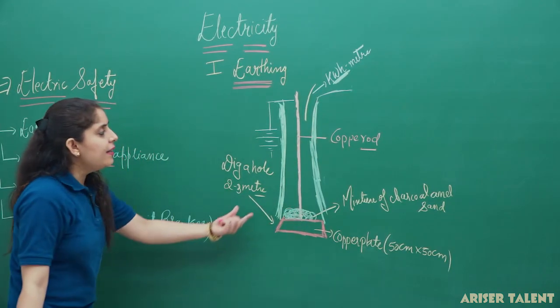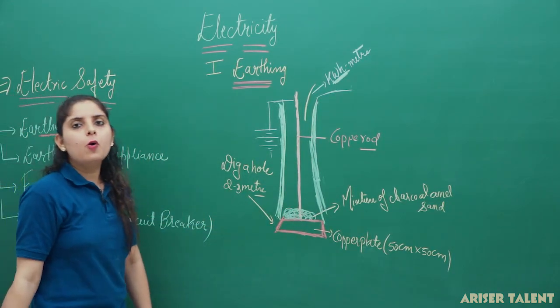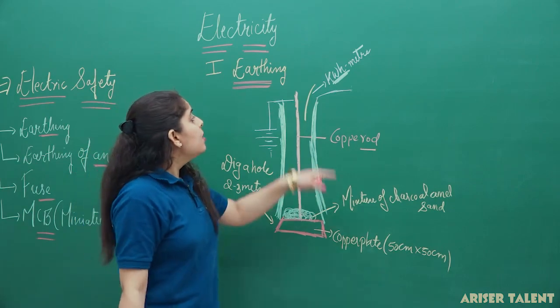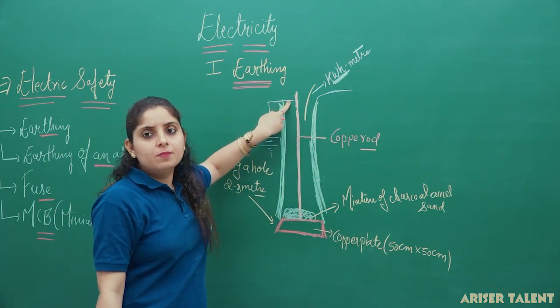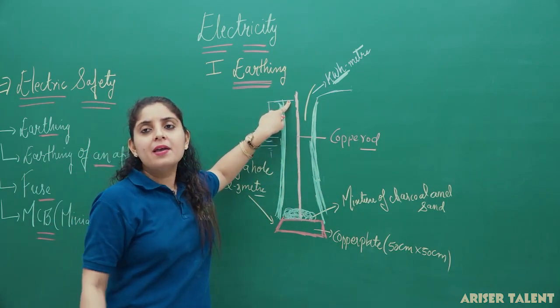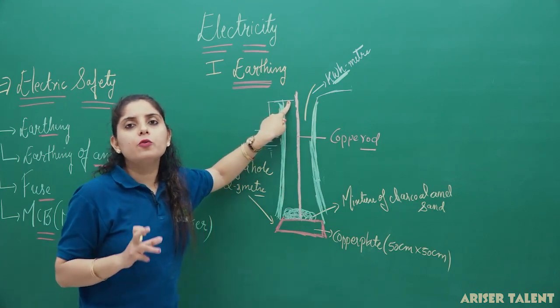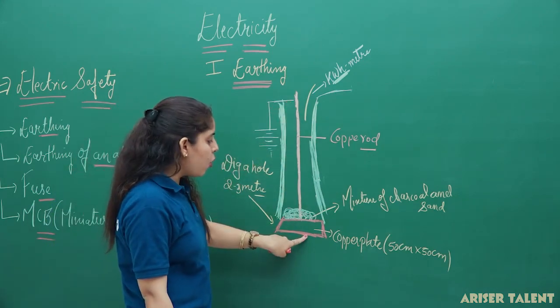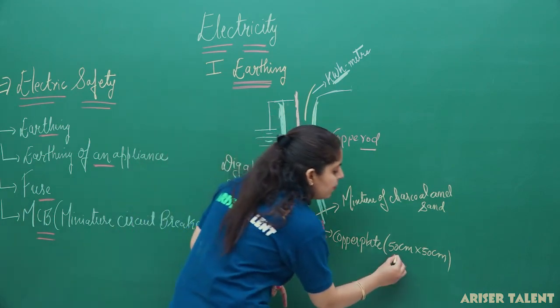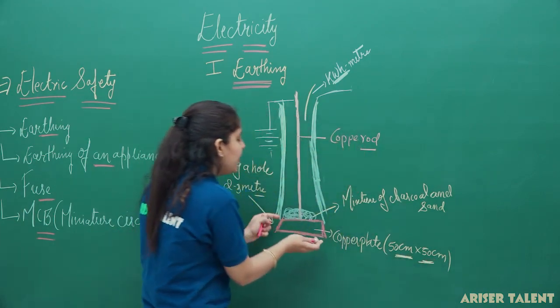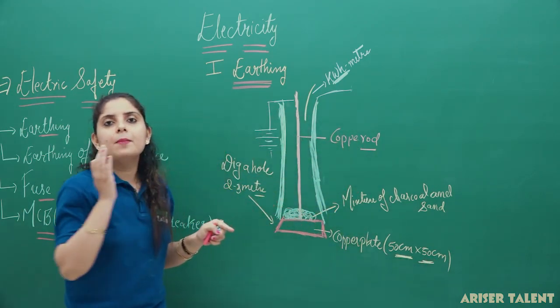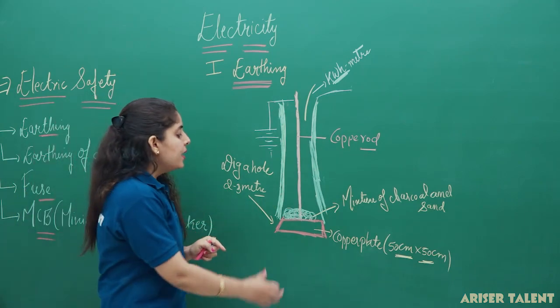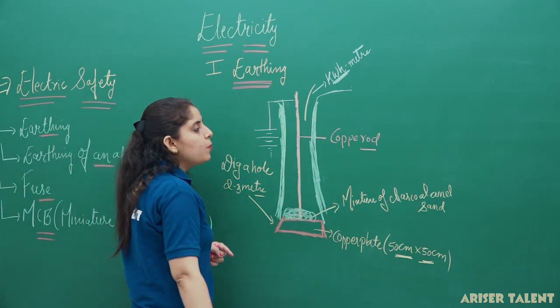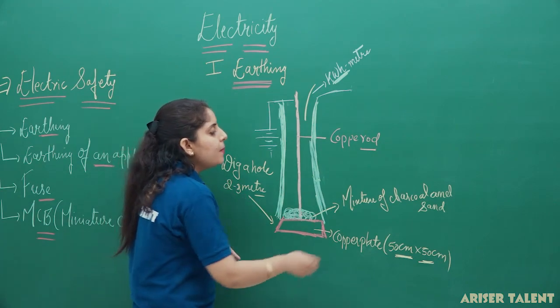In that 2 to 3 meter hole, you put the copper wire. Then at the base of the copper wire, you take a copper plate of dimension 50 centimeters by 50 centimeters, installed at the base of the ground. Now this connection has to be covered with a mixture of charcoal and sand.